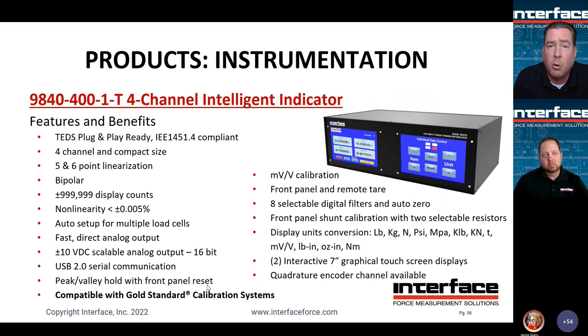should touch on this, a more modernized version of the 9840. The standard version of this is the 9840-400. You'll see that it's of a slightly larger chassis size, but it does go to a more modern touchscreen display. The standard variant has 4 inputs, so it'll take 4 channels of data in. It has the same level of performance, I should say, as the standard 9840. Again, more modernized and more graphical interface.